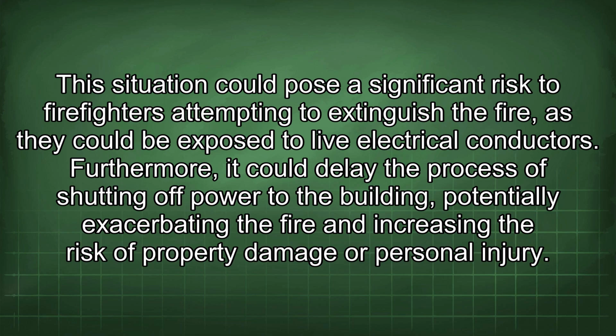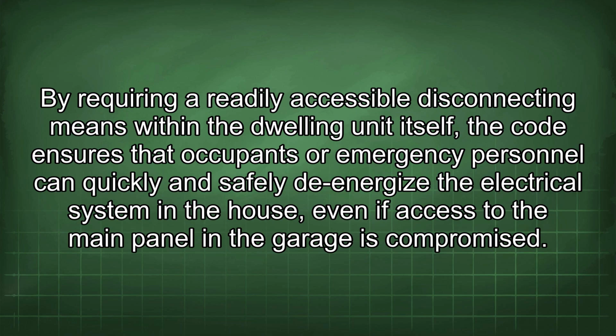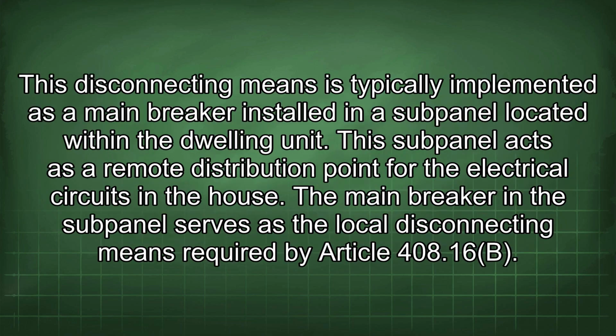Furthermore, it could delay the process of shutting off power to the building, potentially exacerbating the fire and increasing the risk of property damage or personal injury. By requiring a readily accessible disconnecting means within the dwelling unit itself, the code ensures that occupants or emergency personnel can quickly and safely de-energize the electrical system in the house, even if access to the main panel in the garage is compromised. This disconnecting means is typically implemented as a main breaker installed in a subpanel located within the dwelling unit. This subpanel acts as a remote distribution point for the electrical circuits in the house. The main breaker in the subpanel serves as the local disconnecting means required by Article 408.16b.